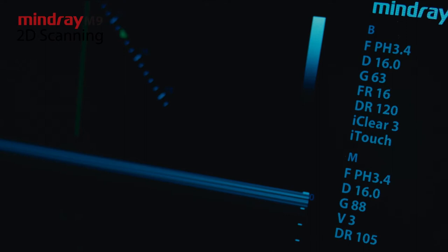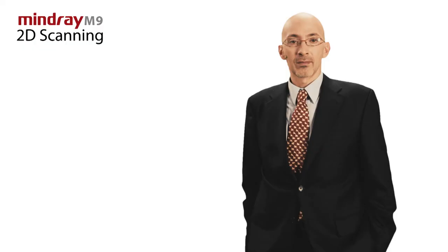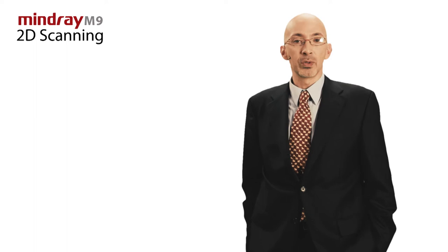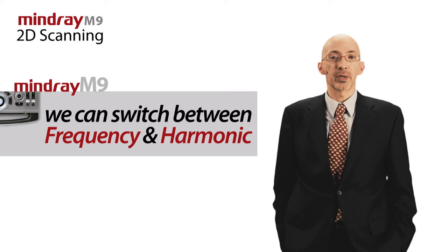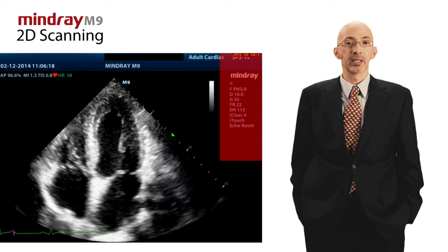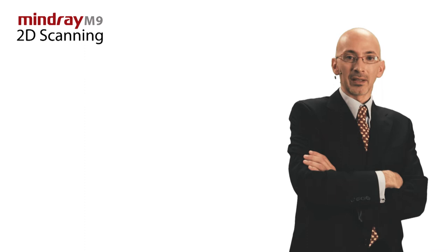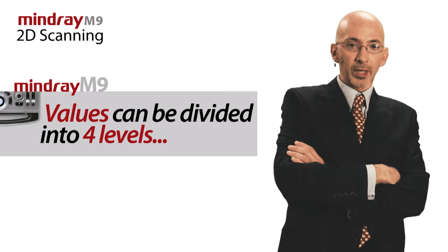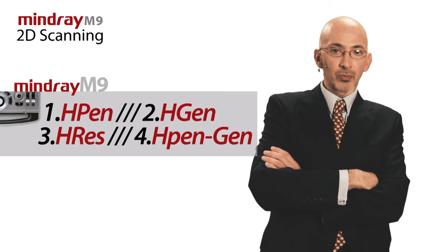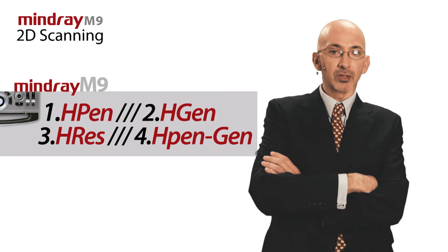In B mode scanning, the image parameter area in the top right corner of the screen displays the real-time parameters. We can switch between the fundamental frequency and harmonic frequency and select the corresponding frequency type. The real-time frequency value is displayed in the image parameter area in the top right corner of the screen, and if harmonic frequency is used, FH is displayed as the harmonic frequency value. Select the different frequency values through Image Quality on the soft menu. The adjusting range of the harmonic frequency values can be divided into four levels: penetration, general mode, resolution, and the mode between penetration and general mode.